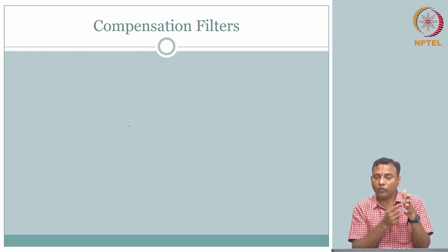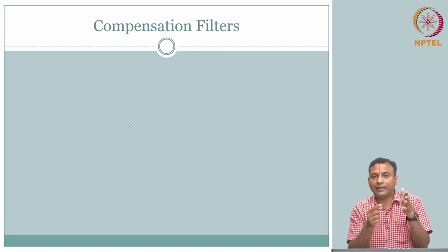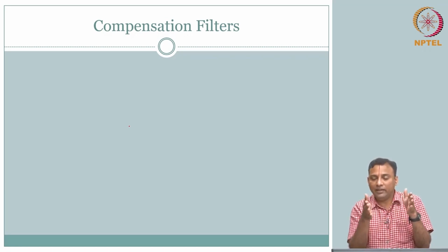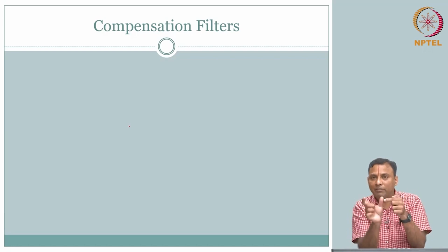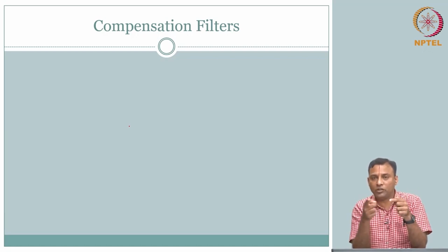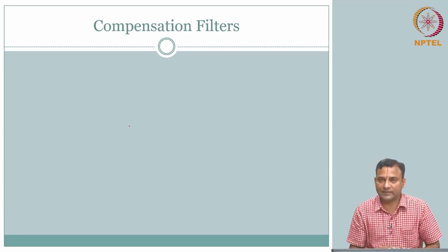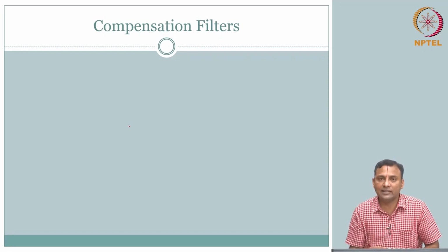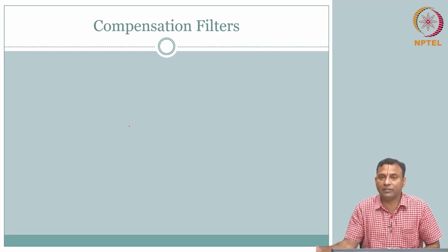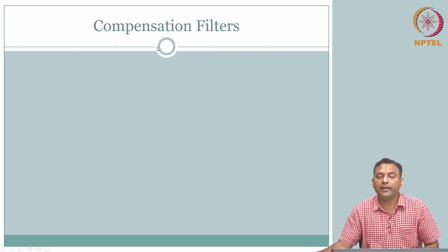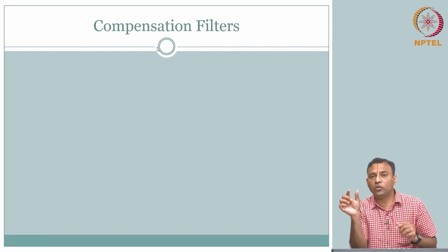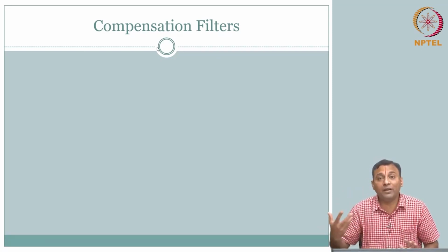I can send the same photons here, but then when it goes in, I could have some material that is shaped to absorb the photons. So when it hits the material, the same number of photons goes through the thickness. Depending on the thickness, I can have an additional compensation filter that is going to allow proportionately the same number of photons to go through the thickness per length. You can normalize it per length.